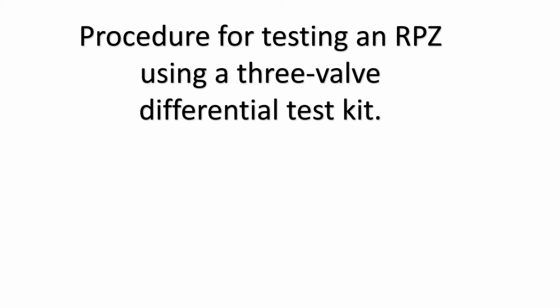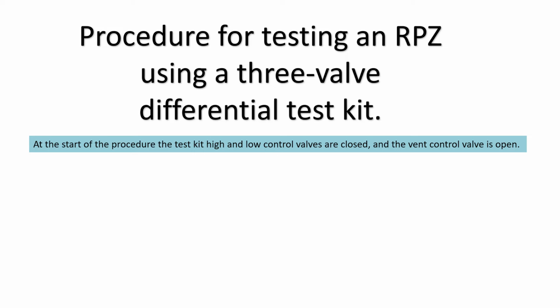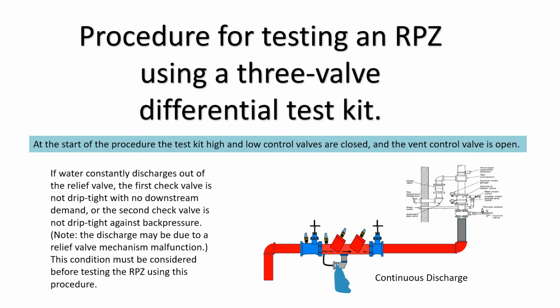Procedure for testing an RPZ using a 3-valve differential test kit. At the start of the procedure, the test kit high and low control valves are closed, and the vent control valve is open. If water constantly discharges out of the relief valve, the first check valve is not drip tight with no downstream demand, or the second check valve is not drip tight against backpressure. Note, the discharge may be due to a relief valve mechanism malfunction. This condition must be considered before testing the RPZ using this procedure.